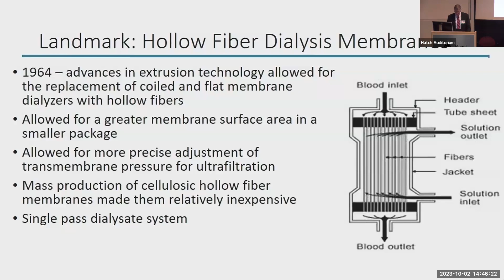Another change that occurred with the evolution to the hollow fiber membranes was the elimination of acetate from the dialysate. So what the problem was is that you have a concentrated powder or solution that has all of the ingredients for your final dialysate, and then the dialysis machine dilutes it out with purified water so that you ultimately get the final concentration of the dialysate that you're looking for. Well, the problem is that calcium and bicarbonate don't play well together in the concentrated solution. They precipitate into calcium carbonate.